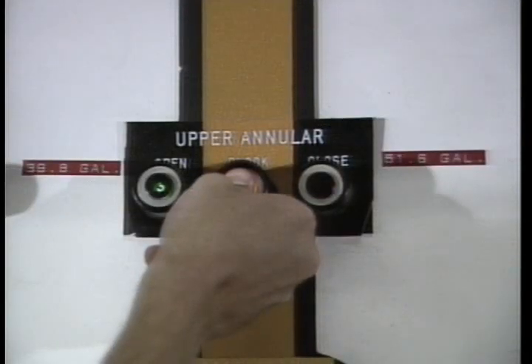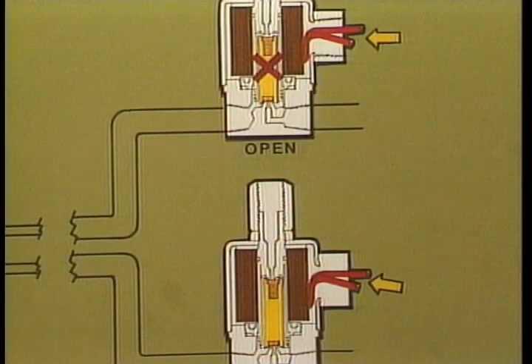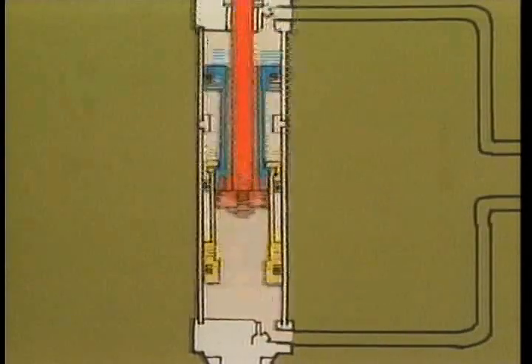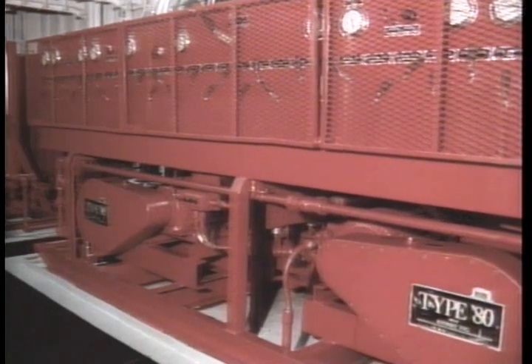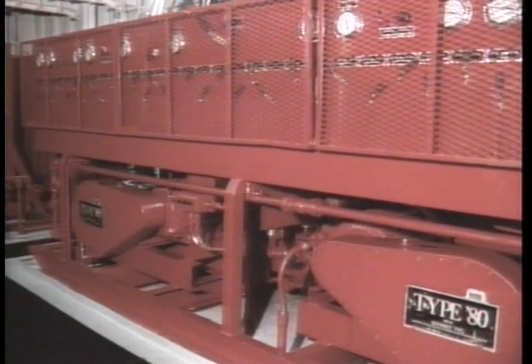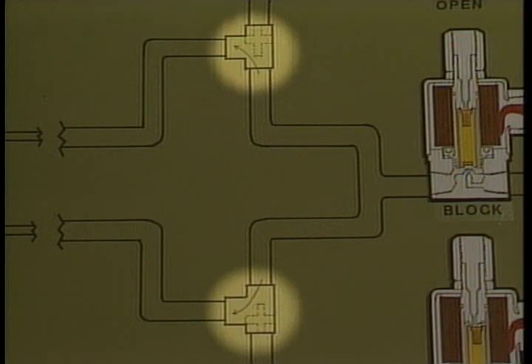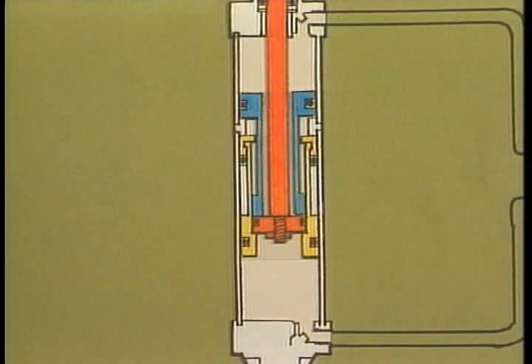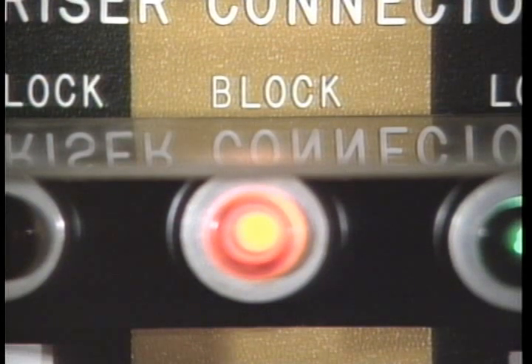When pushing the block position, keep in mind that both open and close solenoids are energized. If the open solenoid happens to be inoperative, operating the system could close the ram or annular that was functioned — be sure to think about what's happening downhole before pushing block. The Koomey system manufactured by Koomey Incorporated utilizes a third solenoid for the block position. Pushing the block button energizes the block solenoid, which allows air to pass through two shuttle valves, acting on both ends of the cylinder, and shifts the four-way valve to the center position. Like the NL Shaffer system, the block light turns on as a result of pressure removal from both the open and closed pressure switches simultaneously.